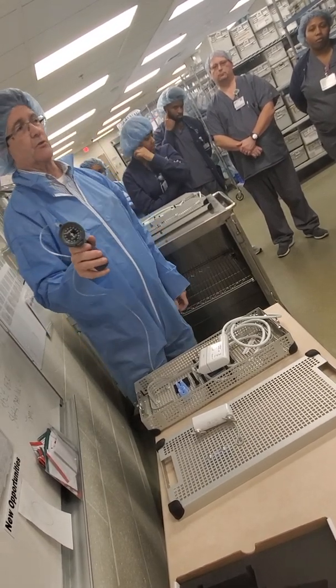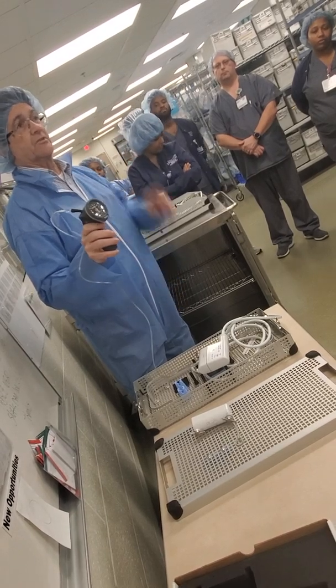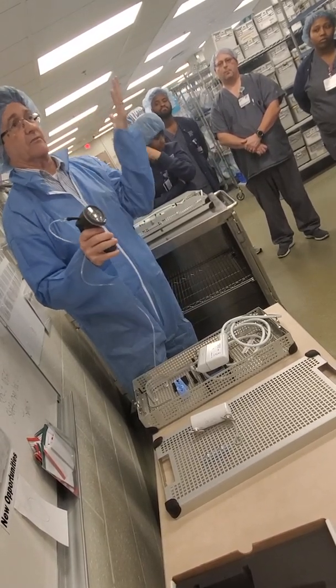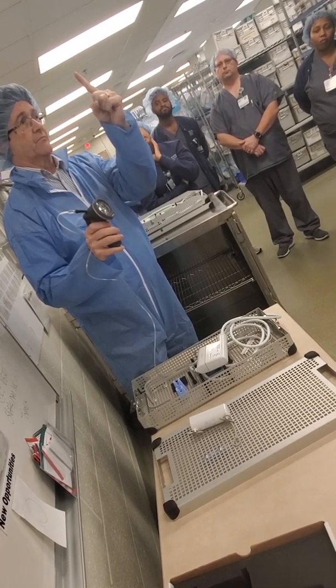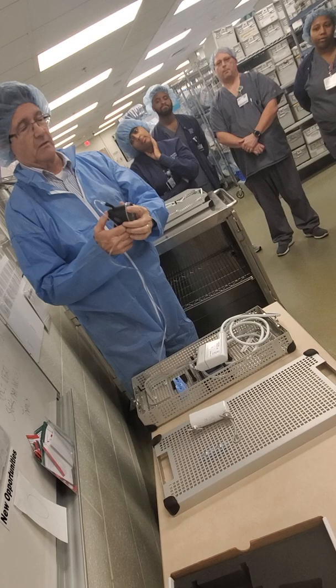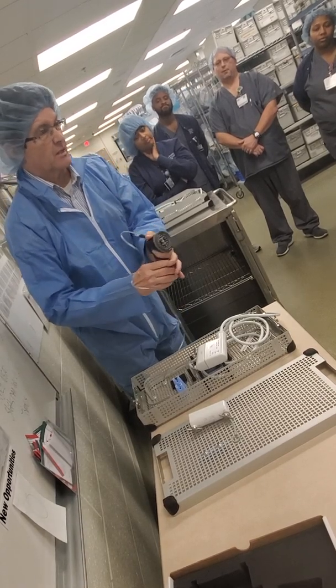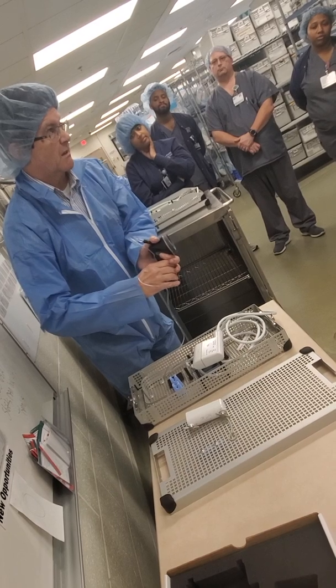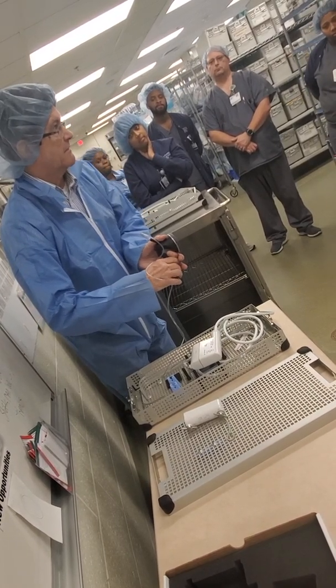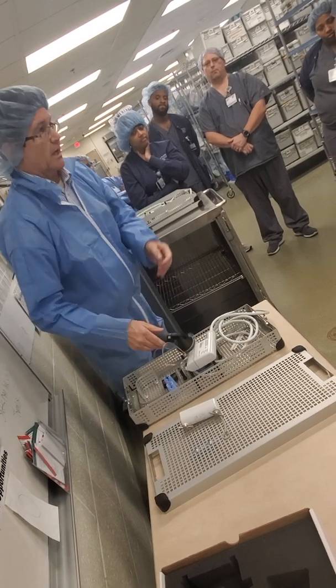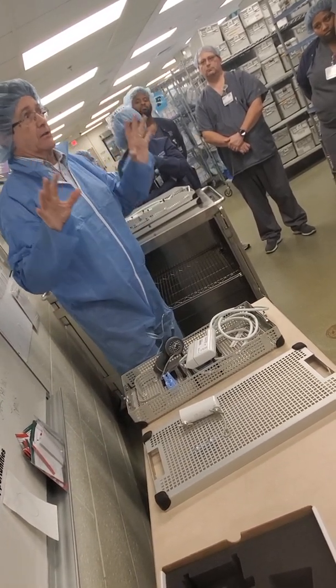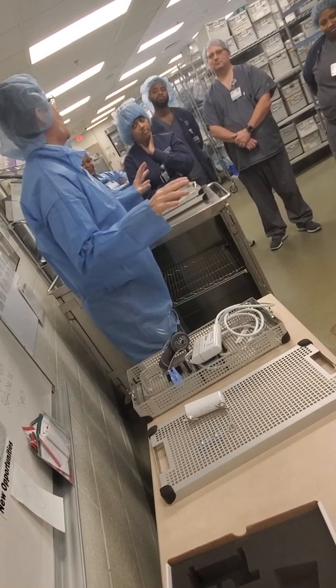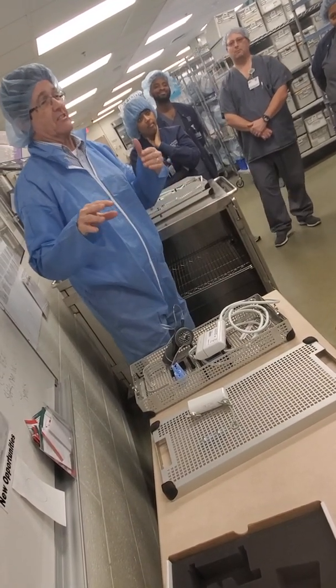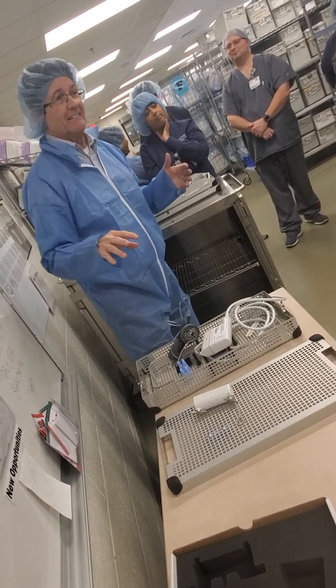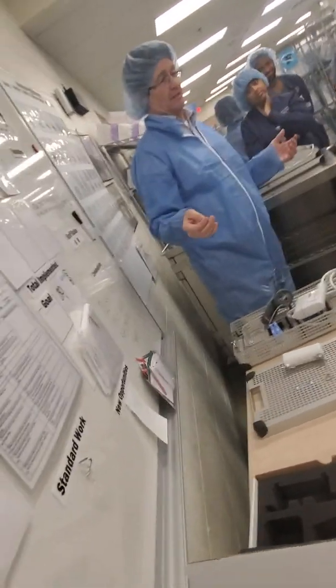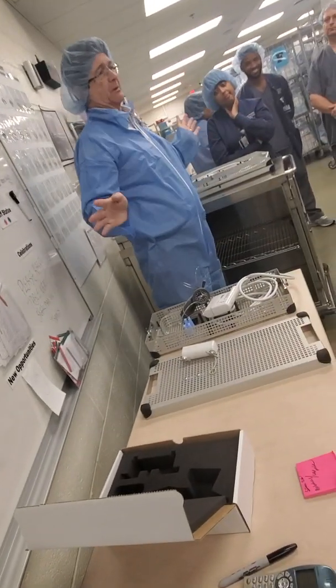All right, now we're just gonna look at it real briefly to make sure the needle is not going down, remember? If you see it while you're watching for 10 seconds and it starts doing this, you know it's leaking, but if it, watch, I'll show you. You'll love this. Watch, I don't know if you can see it, but watch the needle. See that? It ain't going up, is it? Okay, I call that a catastrophic leak. That means there's a hole somewhere. Please God, don't put it in the water. Okay? Because it's going to go all over the place. And if water gets in the probe, it is not repairable.